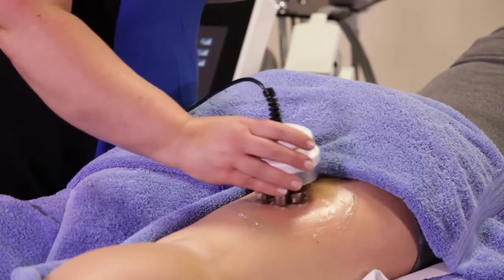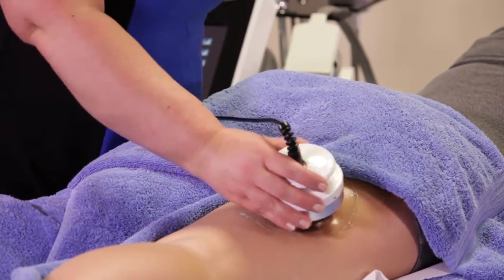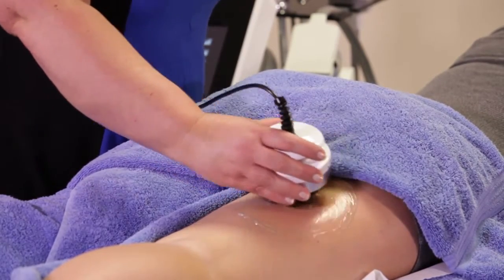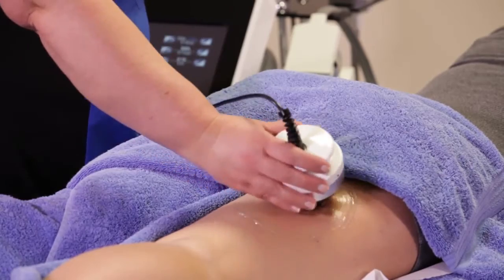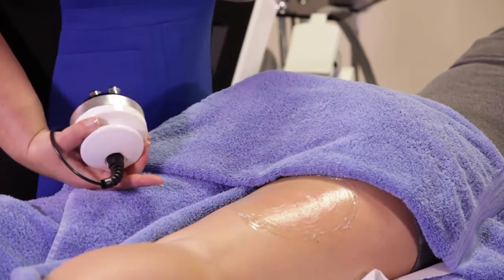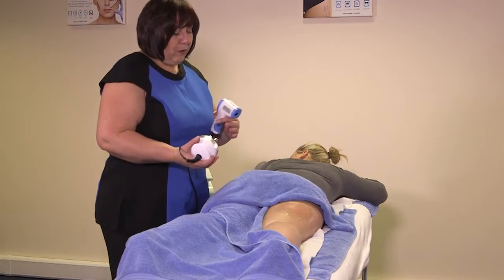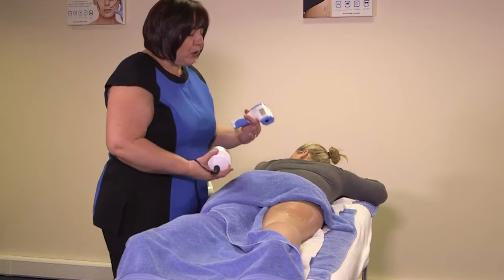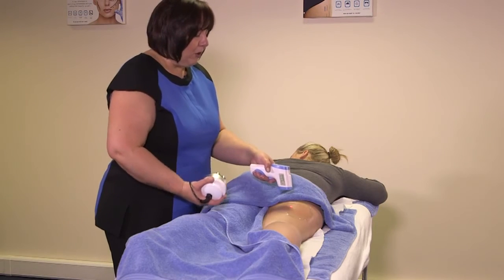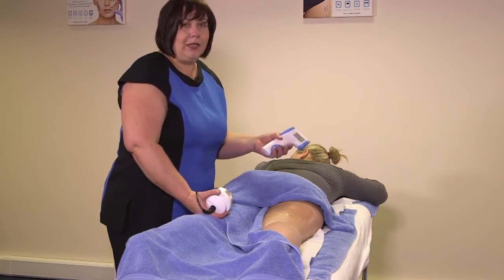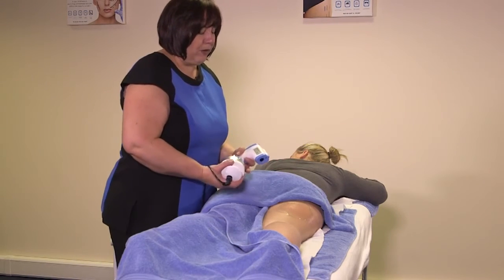Once you've done that for 2 to 4 minutes, what you must then do is keep your head moving, keep it moving all the time. When you're ready, then take your foot off the pedal first and then take your head off the skin. And you can see that there's a nice erythema. Do make sure that whilst you're maintaining your heat, you keep your head on the skin all the time, because as soon as you come off, the skin temperature drops very, very quickly. So I've only been off now for a few seconds, but I'm down to 39 degrees. So keep it on the skin all of the time.